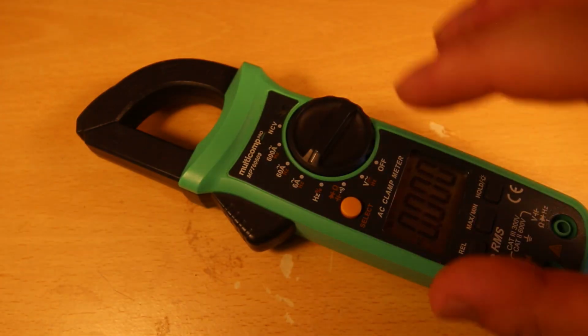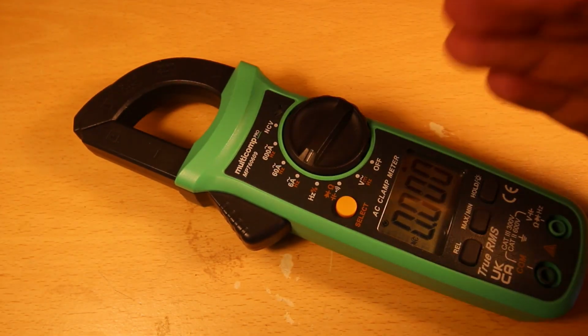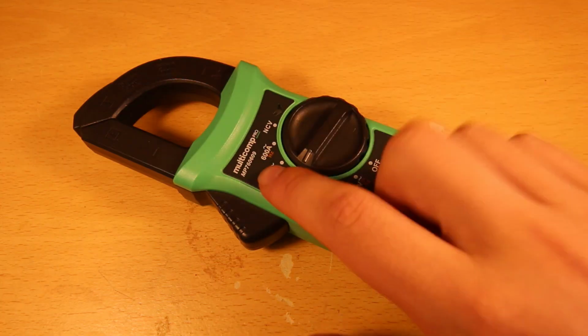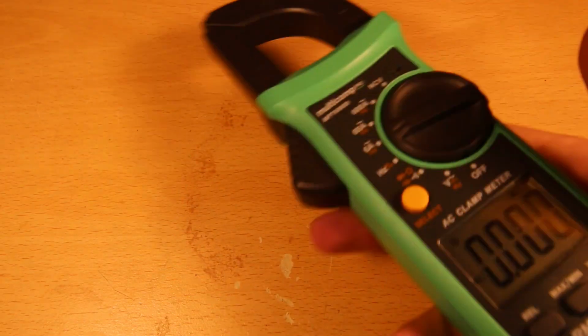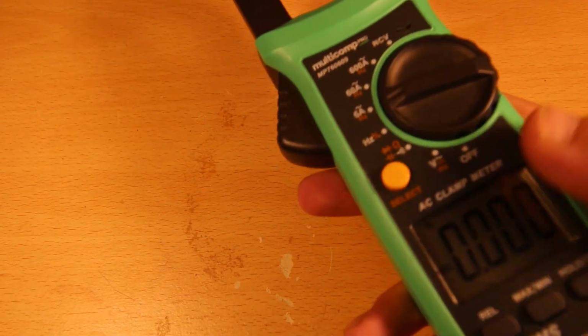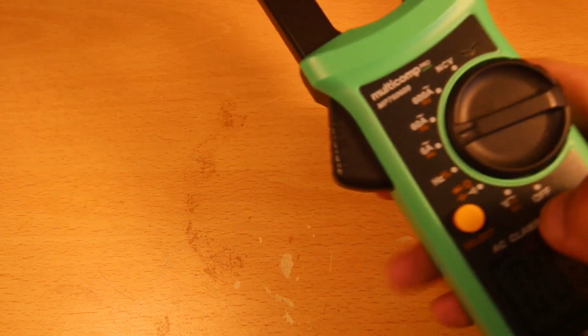And before doing any work on any TN installation, so TNS, TNC-S, anything like that, you should always check the current in the bonding cables and the main earth current with a non-contact current clamp. You can get ones that are designed for measuring leakage currents, which are much more sensitive. This one here is designed for measuring like 600 amps. It's my one that I use for measuring current in tails and so on, but it will work to tell you if there's a significant current flow through the protective conductor. And obviously if there is, stop work immediately, don't touch it. But yeah, unfortunately there's not a huge amount we can do.